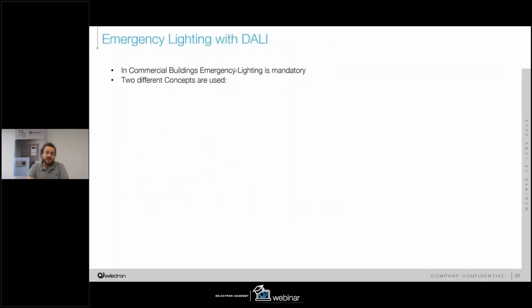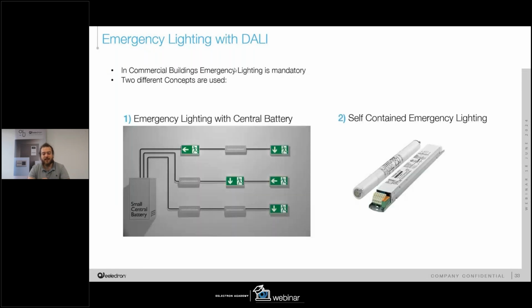Going ahead, I want to discuss very fast also the emergency lighting system, since a lot of times there is a request to integrate the emergency lighting control system with DALI, and thanks to the DALI protocol this will be very easy. So first of all, we have to keep in mind that we have two different kinds of emergency lighting system, starting from the emergency lighting system with the central battery.